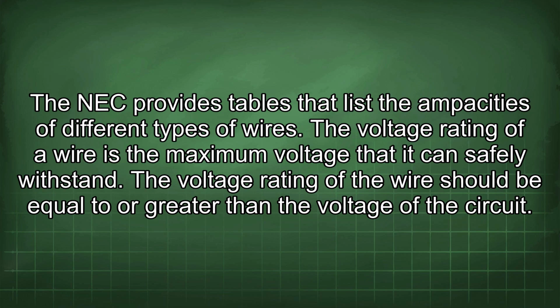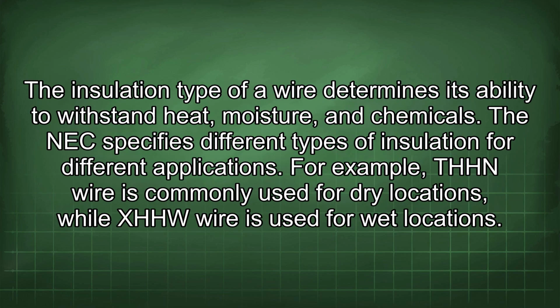The voltage rating of a wire is the maximum voltage that it can safely withstand. The voltage rating of the wire should be equal to or greater than the voltage of the circuit. The insulation type of a wire determines its ability to withstand heat, moisture, and chemicals. The NEC specifies different types of insulation for different applications. For example, THHN wire is commonly used for dry locations, while XHHW wire is used for wet locations.